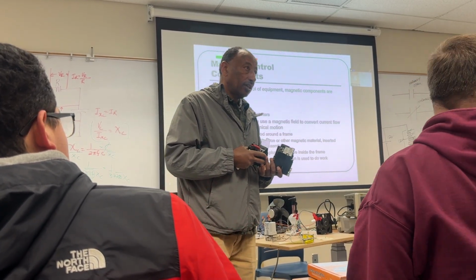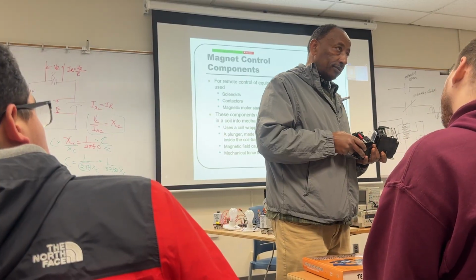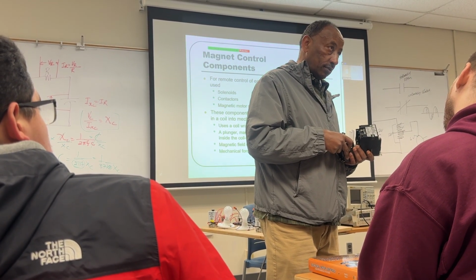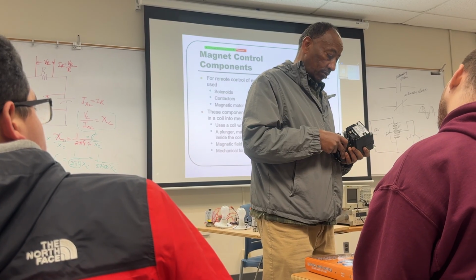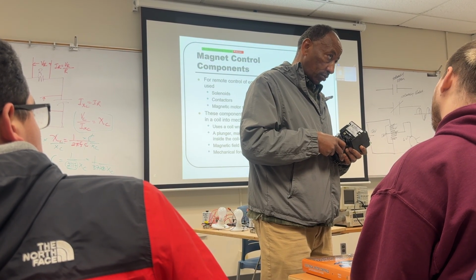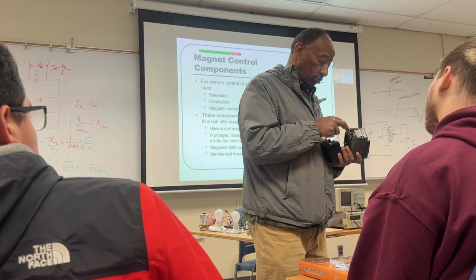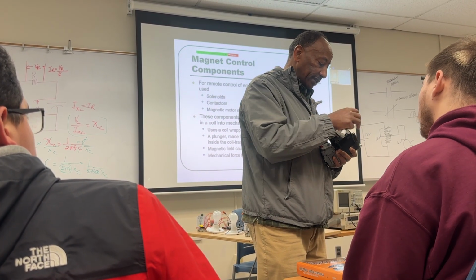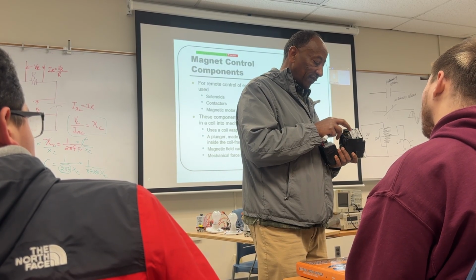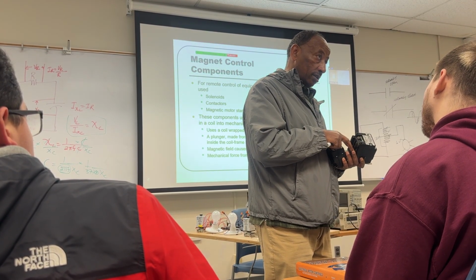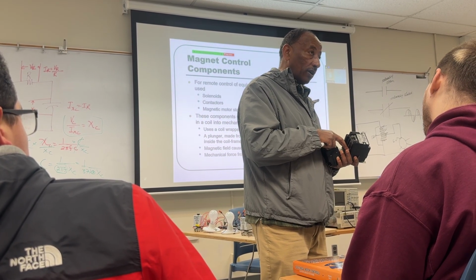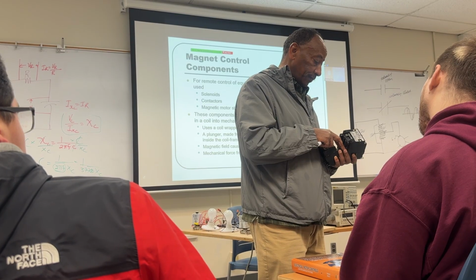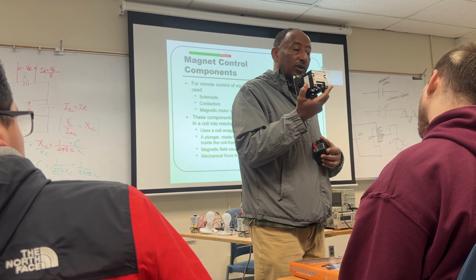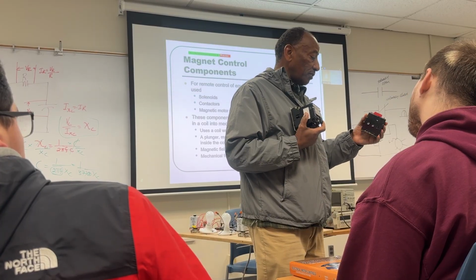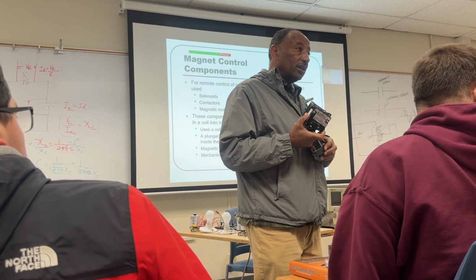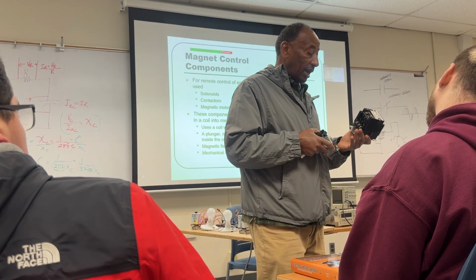If you're troubleshooting one of those, are you going to check continuity from top to bottom, or check resistance? Say you think one of those is going out, something's not working, how are you going to troubleshoot that? Right. If I connect here and then activate this, if it doesn't close, there's no power here. So it's a power test. Those could be for lighting contactors, for heating and all that stuff. But if it has a motor, it has to have this. Do those go out? No, this actually lasts you a long time.